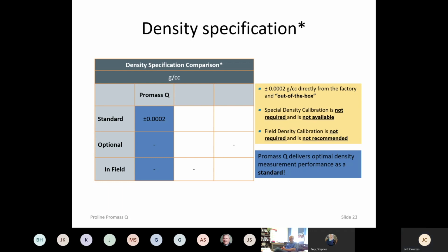So basically 0.0002. Most of you take density and you convert it to some percent concentration. If you're looking at density, you're looking at a concentration of something, or maybe it's an evaporation process and you're using that density number to tell you how efficient your evaporator is running, make sure you're delivering the product that you said you're going to deliver. So the out of the box density accuracy of this meter is 0.0002 versus the out of the box density accuracy of some of our other meters is 0.02. Okay, the reference accuracy of those meters, if we were to have that meter in the lab, would be 0.0001.